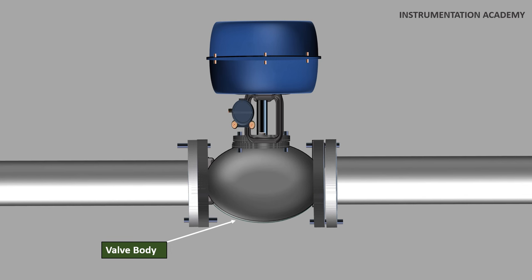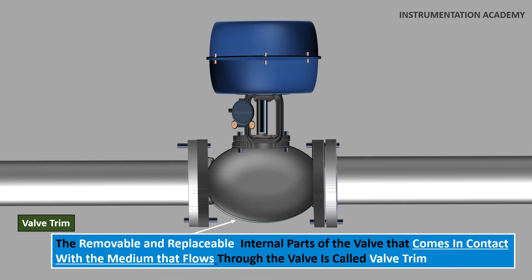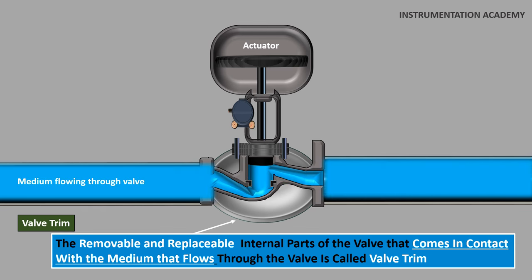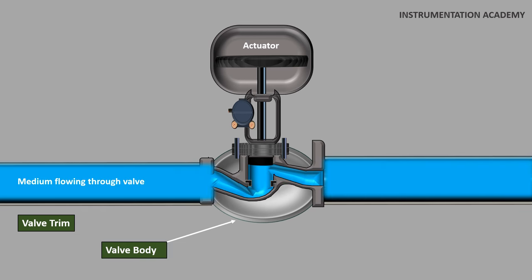Valve trim. The heart of the control valve is the trim. The removable and replaceable internal parts of the valve that comes in contact with the medium that flows through the valve are collectively termed as valve trim. Valve trim includes valve seat, valve disc, internal springs etc.